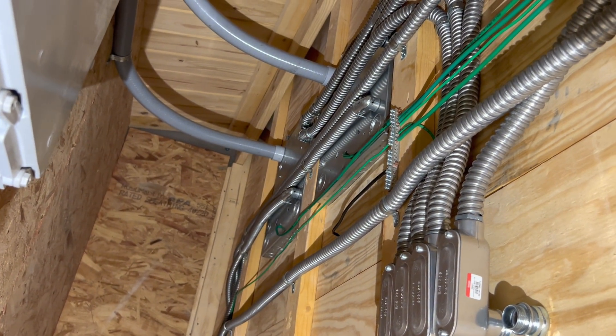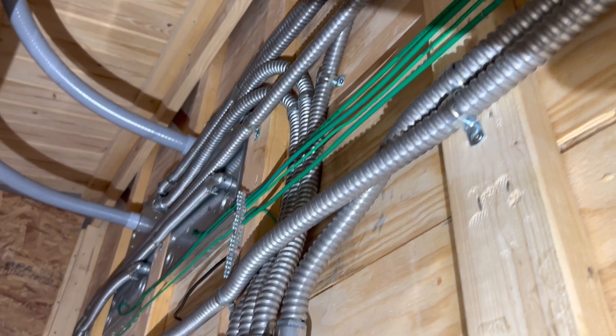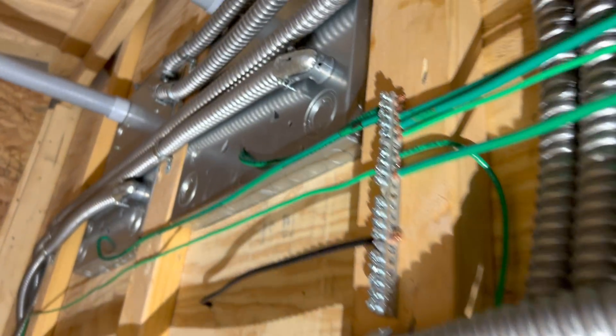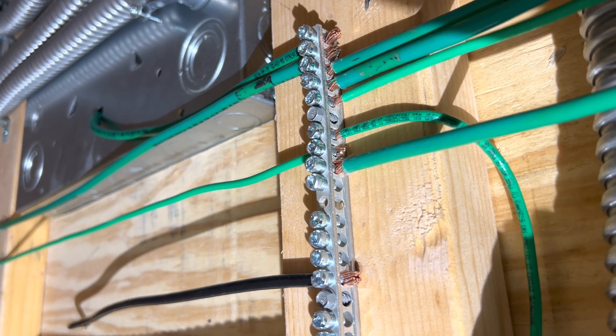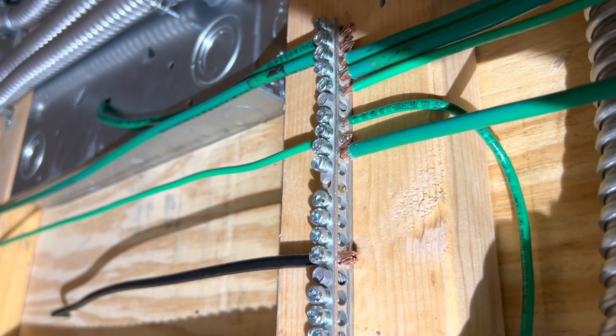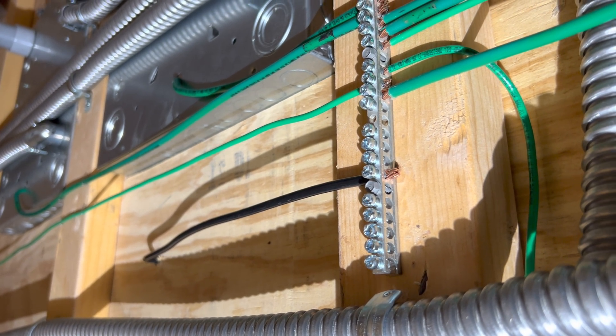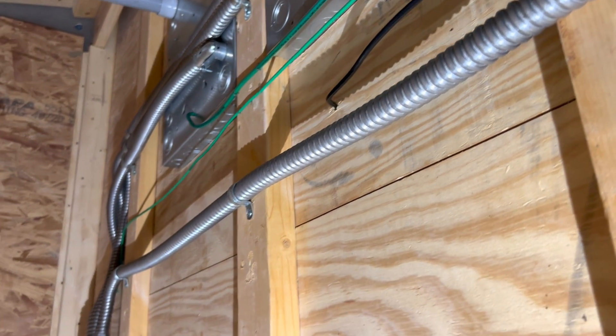One last thing before I end this video — besides asking you to like, subscribe, and share — I want to show you the wiring behind these panels. In another video on my house I showed hard piping; here we decided to use flexible conduit. You can see all these ground wires coming in and tying into this ground lug. From there, a six-gauge ground wire runs back to the main grounding lug at the main distribution panel, because we only want to tie into a ground in one location and run everything back to that single point. That'll be tied in very soon.